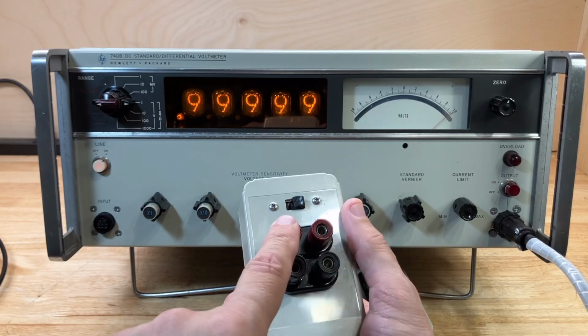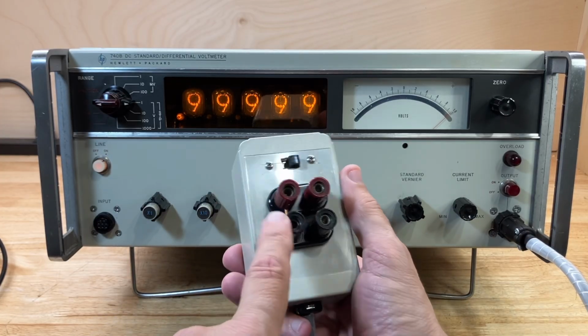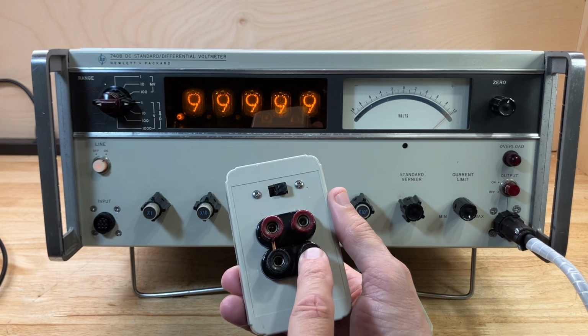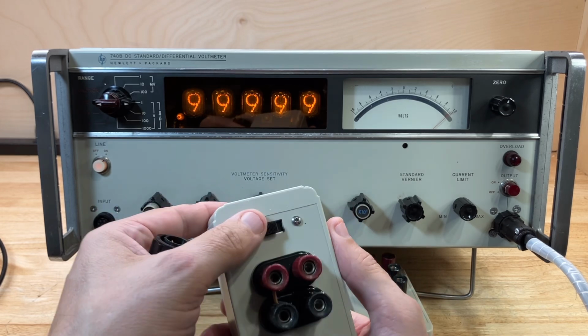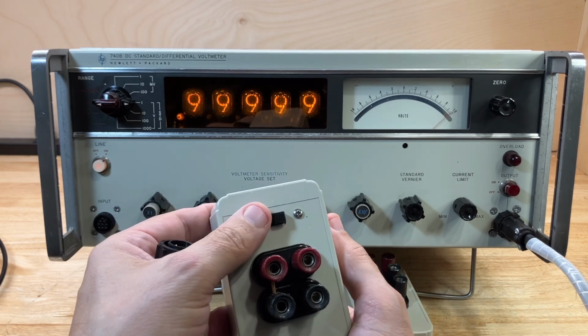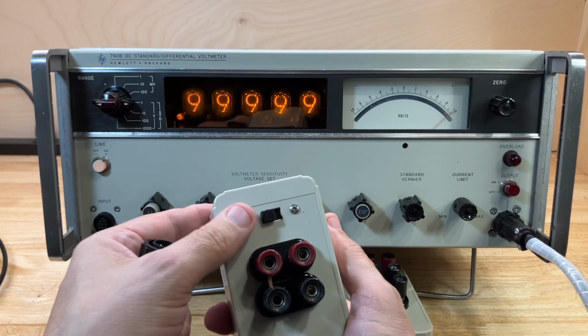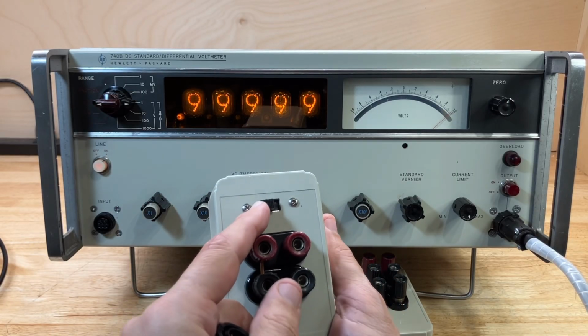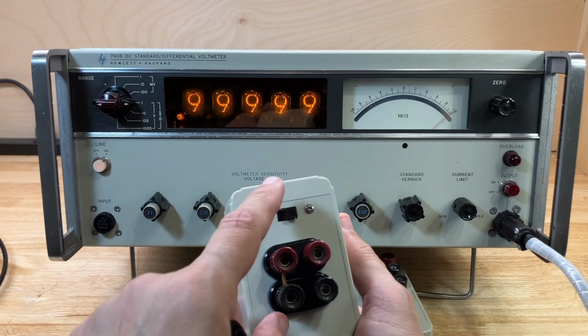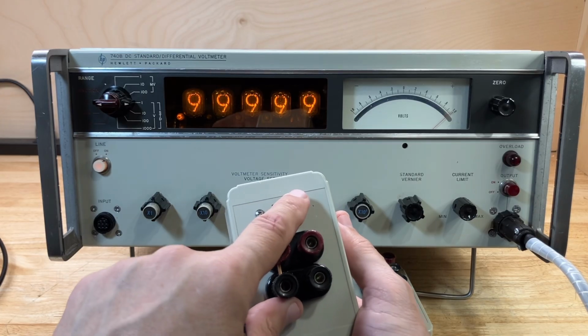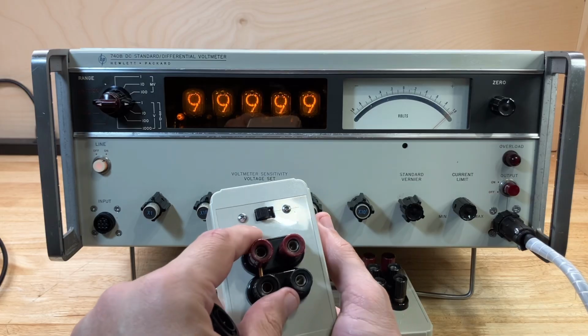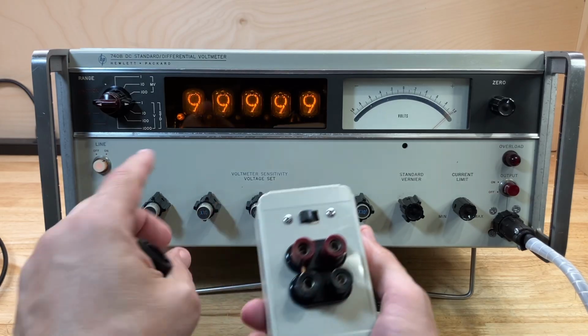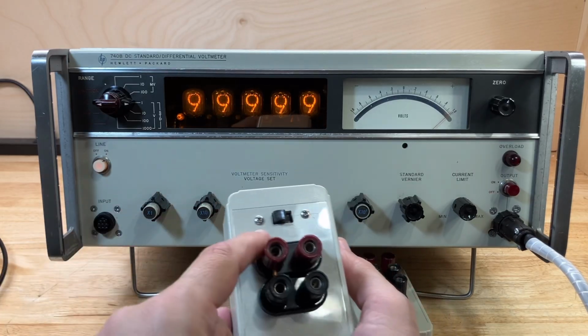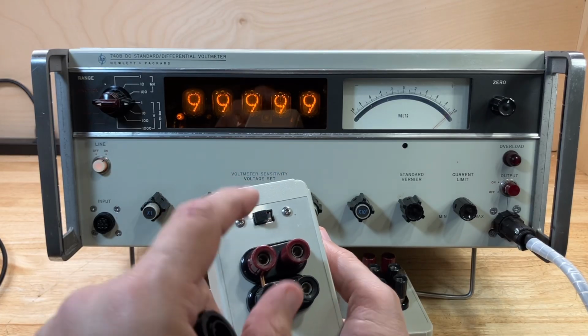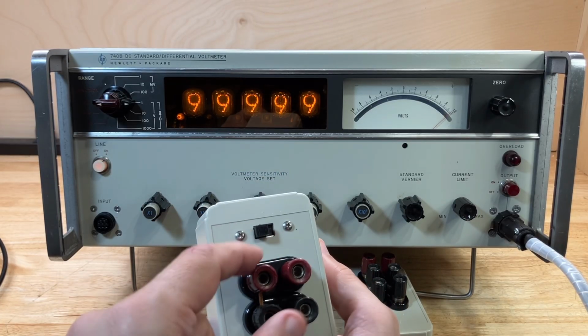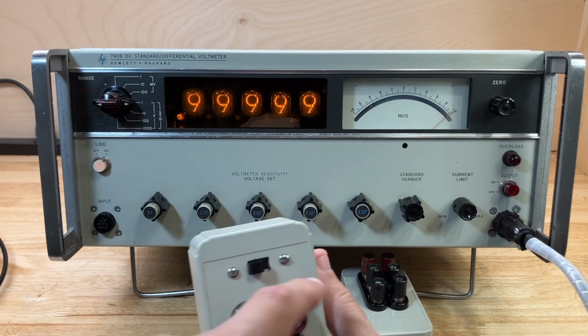This one has a high and low input terminal, as well as a guard terminal and an earth ground terminal. There's a switch on here to switch between infinite input impedance and 2 megohm input impedance. What that switch is used for is because it basically has an infinite input impedance, this instrument over here at the input terminal.